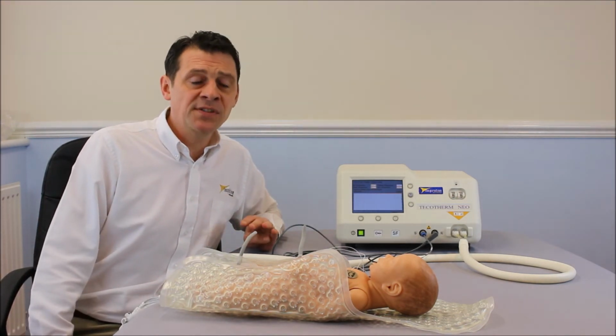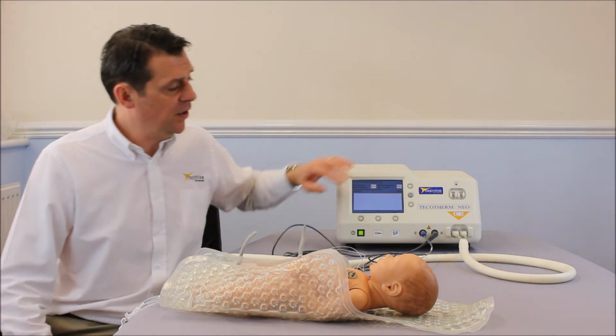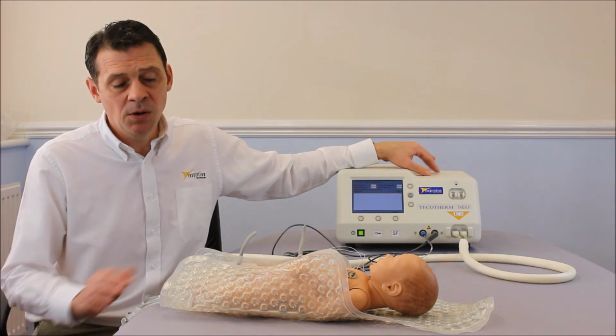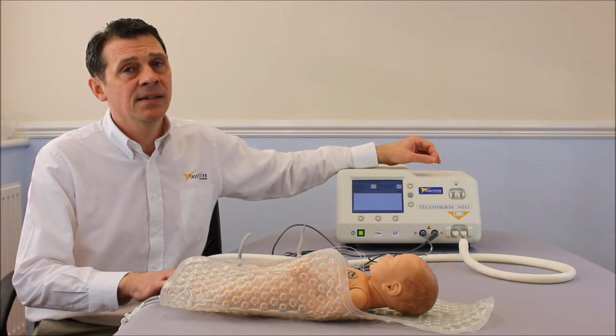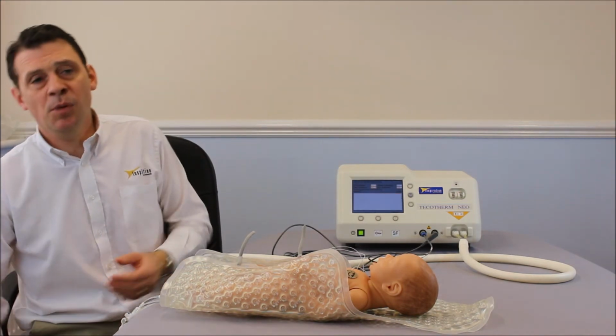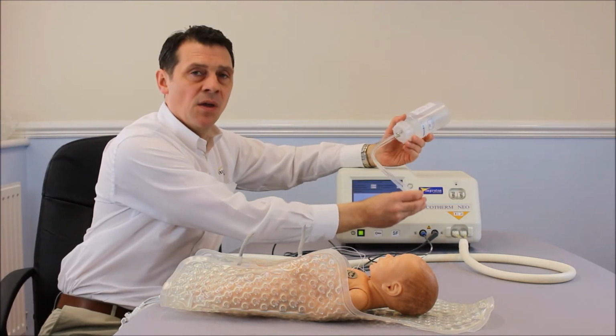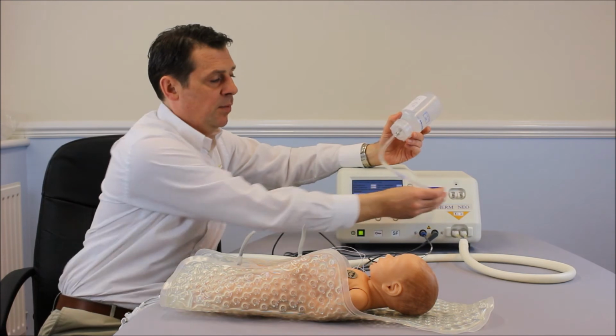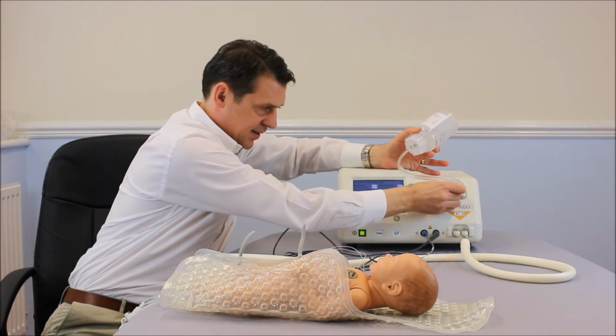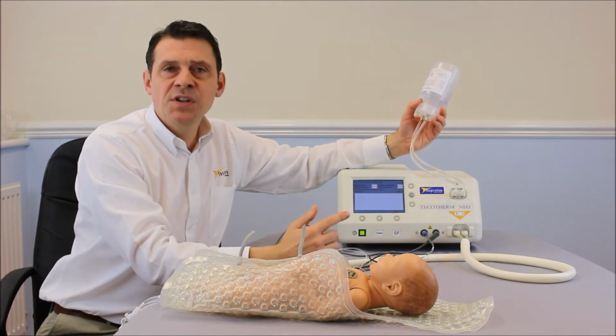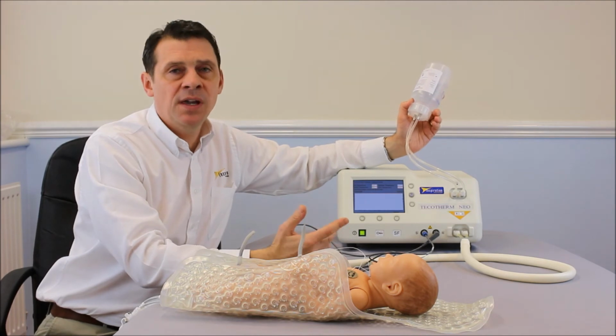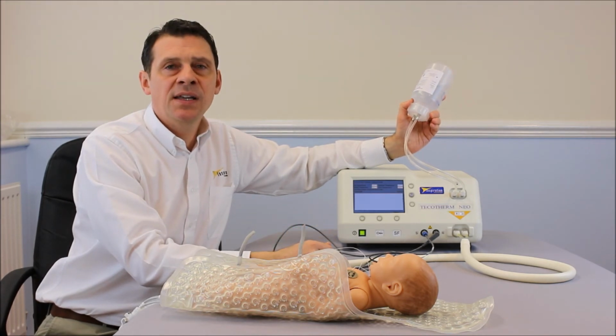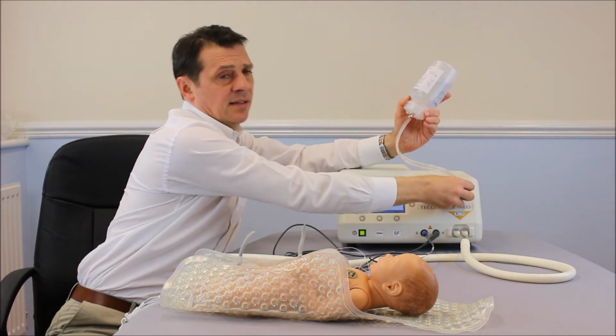Another alarm that can go off is the low fluid level. That's because we've either got the reservoir in here too low, or the mattress has got too little fluid in it. What we need to do again is top up, as we have done before, connecting both sides to the top buttons here, like so. Once you've done this for a number of minutes, it should also then recorrect and take the alarms away, and then disconnect, and you should be happy to continue.